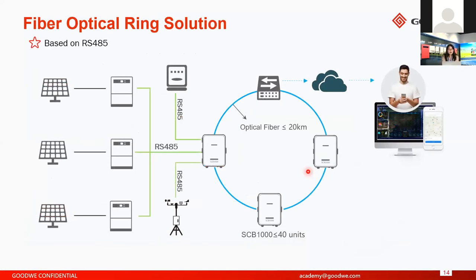And next, I'm introducing a fiber optical communication monitoring solution. First, it is based on the RS-485 communication method. As you can see from the diagram, the inverter to our data logger SCB-1000 is through RS-485, and each SCB-1000 can collect up to 40 units of inverters. But if you have more than 40 inverters in one project or in a whole big project, you can use several SCB-1000 to form a communication ring solution.